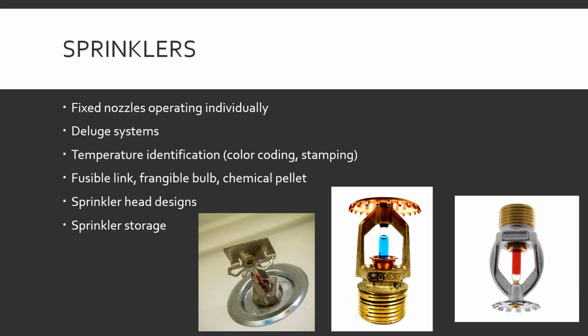Deluge systems. Deluge. Words are hard. These are in more of your high danger areas, aircraft hangars, oil refineries, plants, that kind of thing, where all the sprinkler heads are open and the alarm goes off or a sensor is tripped and water goes in and water's coming out of everywhere. They're open all the time. There's just no water to them until the system is activated.